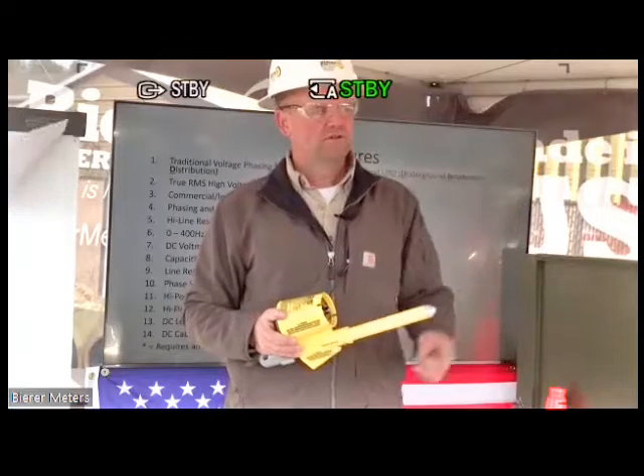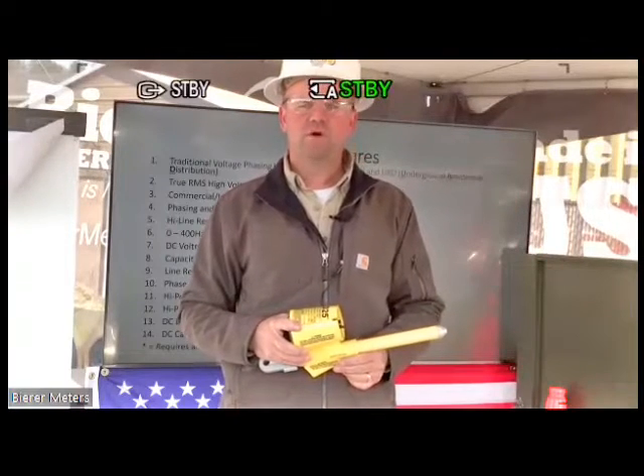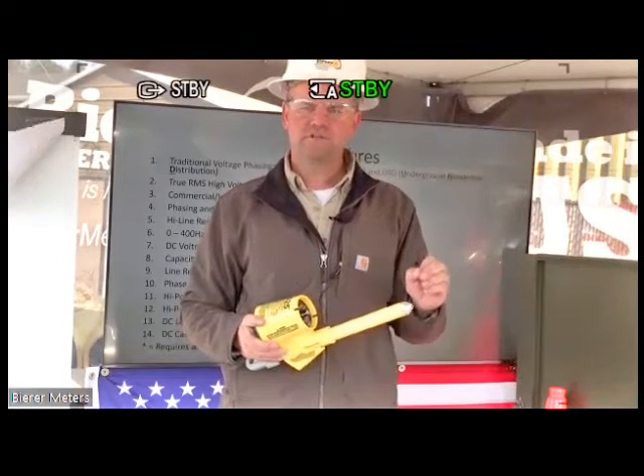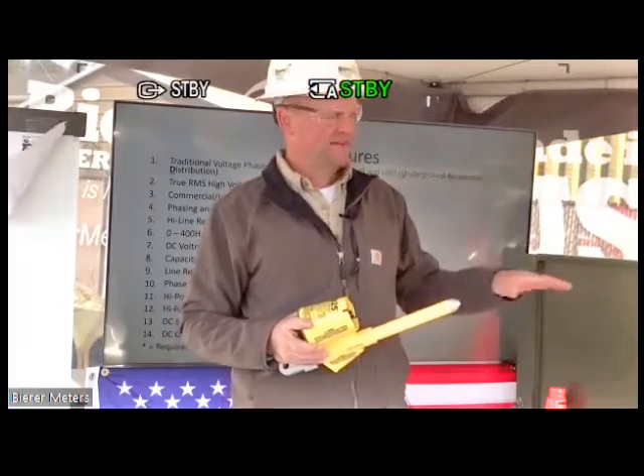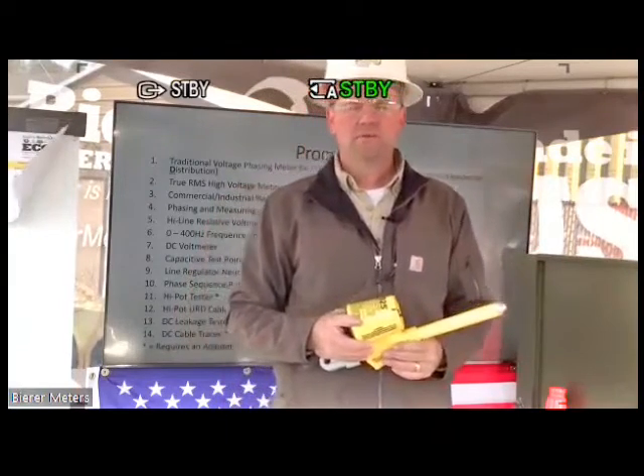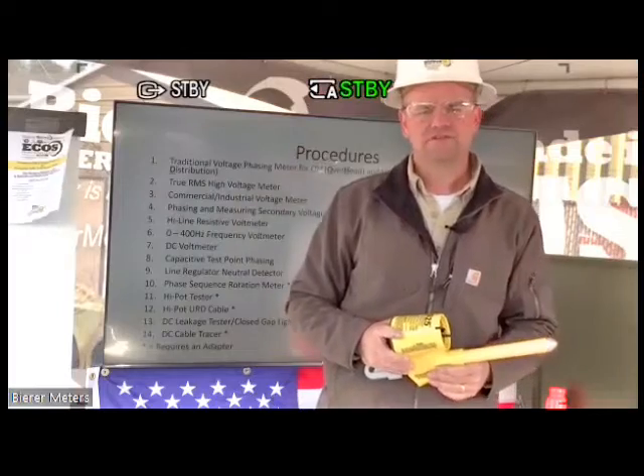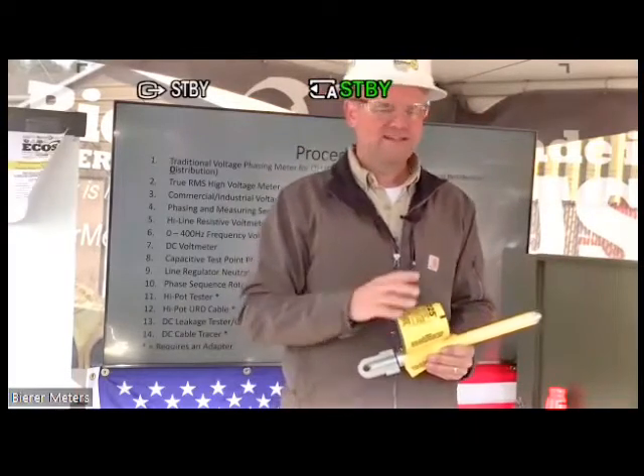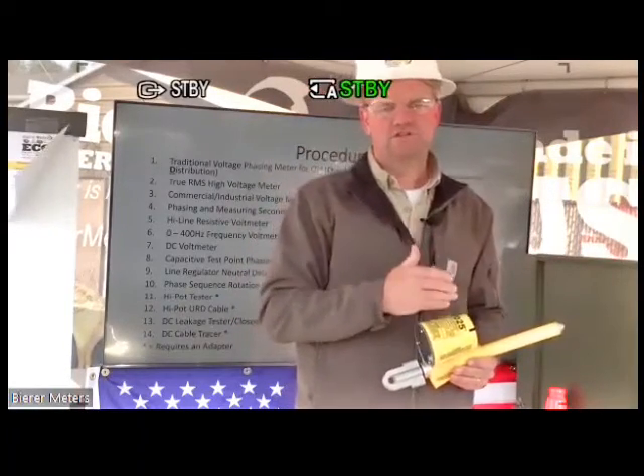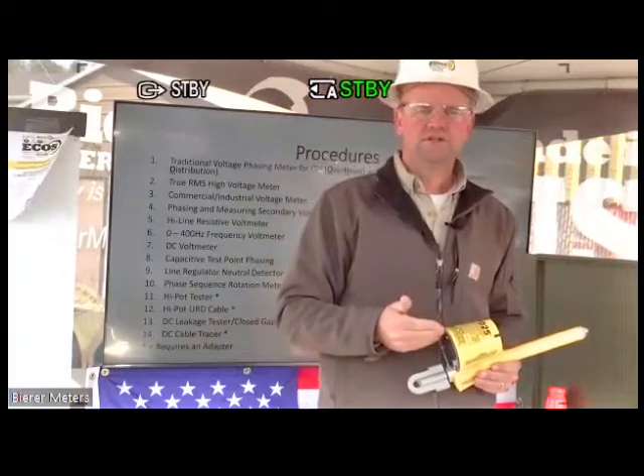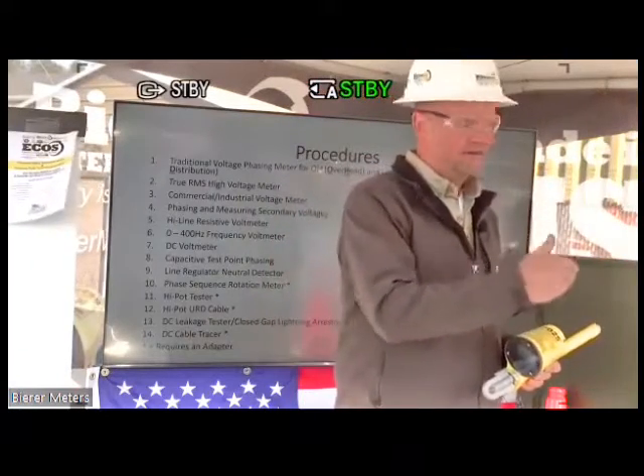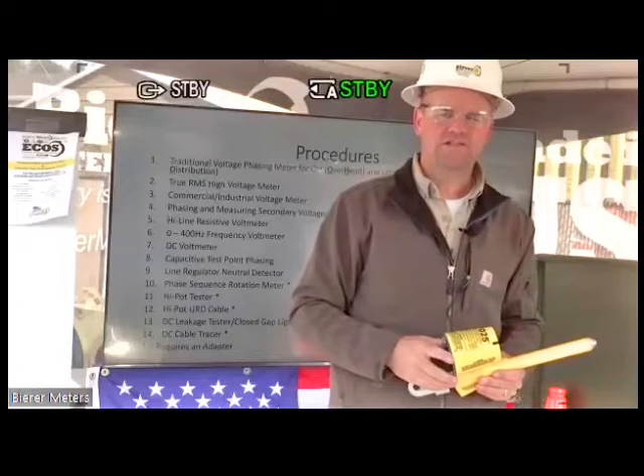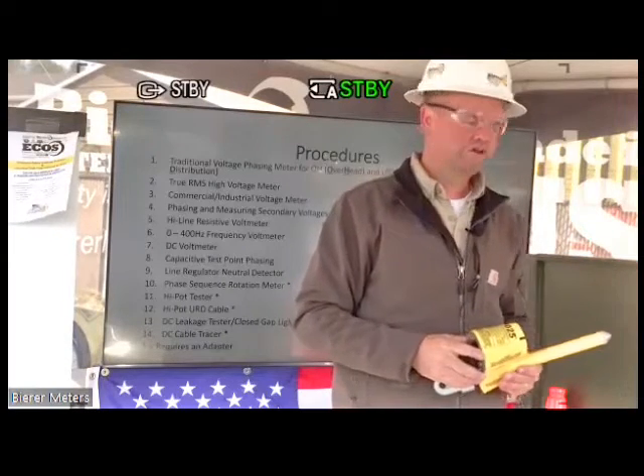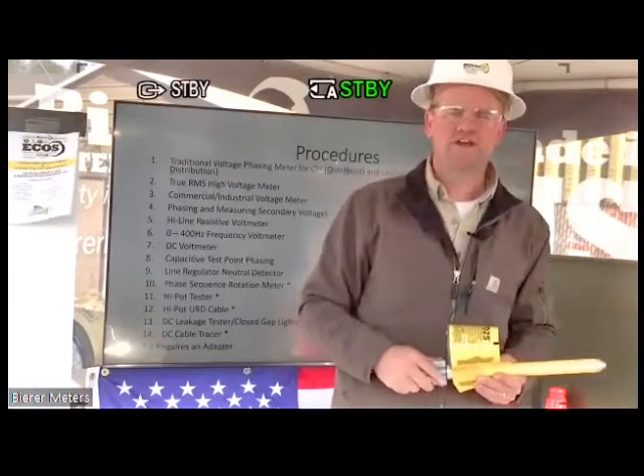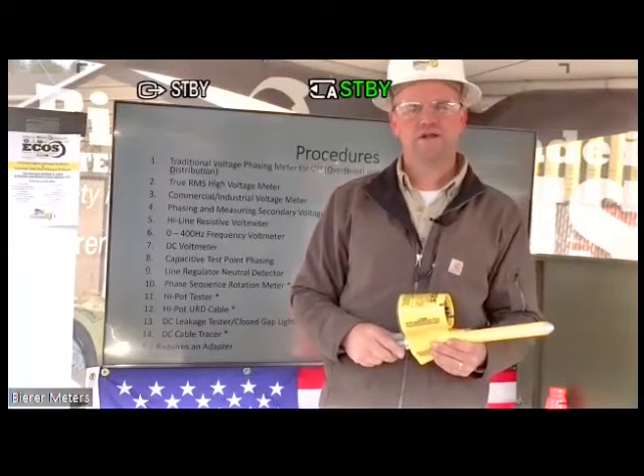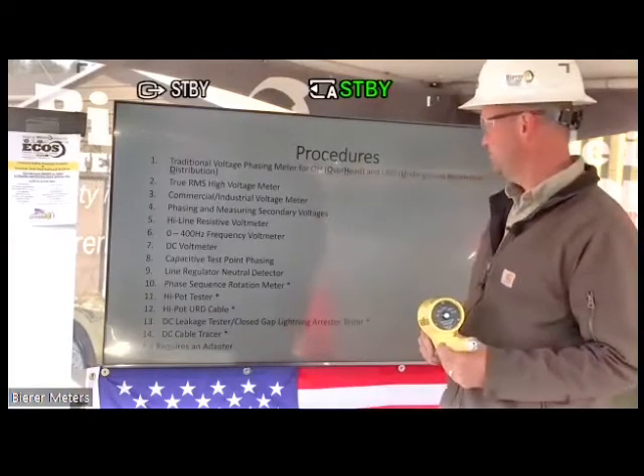We actually have another three-phase pad mount in here where one of the Elastimold capacitive test points has gone bad. It's not in this cabinet, it's in another cabinet, but we've determined that it's gone bad. So again, you want to test each capacitive test point, make sure it's good, phase to ground, and then compare that phase to ground on your other capacitive test points, make sure they're all good, and then you can go phase to phase and determine what's in phase and what's out of phase.